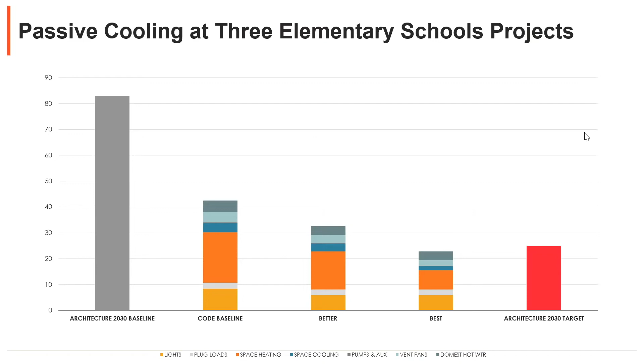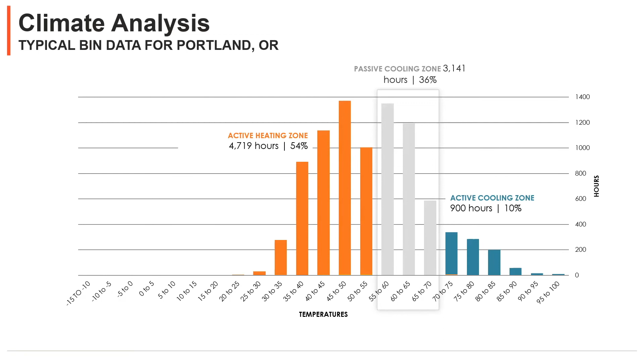So what they did was, this is our climate bin for the Portland metro area. Your hours per year that you would be able to do passive cooling in. And you see about 3,000 hours, just a little bit over. And this was with your code baseline envelope. And there's your active heating hours and your active cooling hours. So this was more like your economizer hours in Portland, if you were to graph it that way.